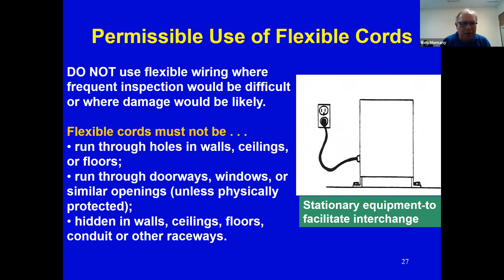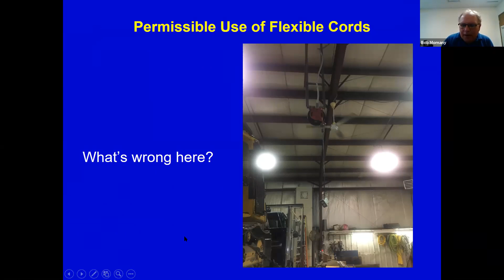And don't let your cords also create a hazard, trip hazards where they're going across, say, aisleways. This was a picture that I took not too long ago at a business. And as you can see in the business here, I have an electrical outlet box that is being dropped down from the ceiling. And so when you get closer to it, there's a close-up of it. And what you can see is the outlet has been pulled from the wiring or from the cable, and the wiring has been exposed. So that's one hazard right there.